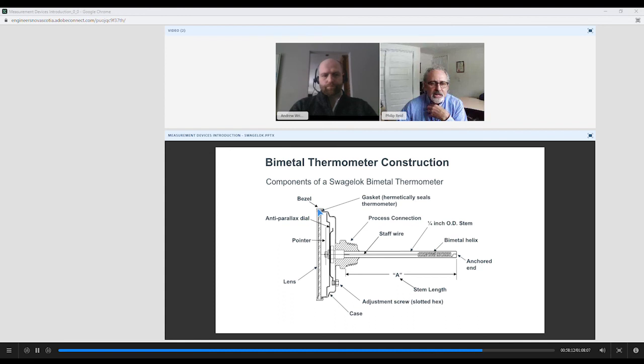We've got a bezel which is gasketed and hermetically sealed to the lens, so you don't get fogging inside the lens. I will come back and talk a little bit about anti-parallax and looking at things on the same plane in just a moment. And then the pointer will be in here. You'll have the lens, and there's various lens materials. You'll have the stainless steel case. They are calibratable, so there's a calibration adjustment screw on the back, and it actually doesn't change anything in here. It actually turns the dial on the face once you have either an agitated ice bath or boiling water.